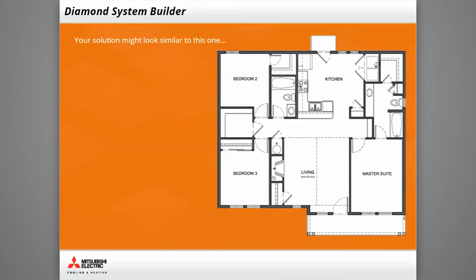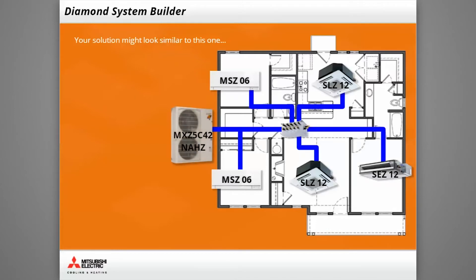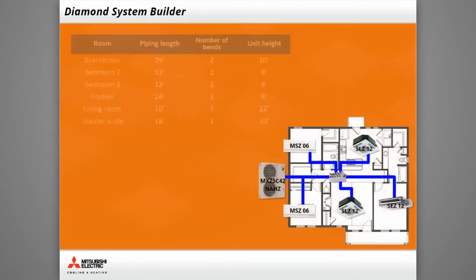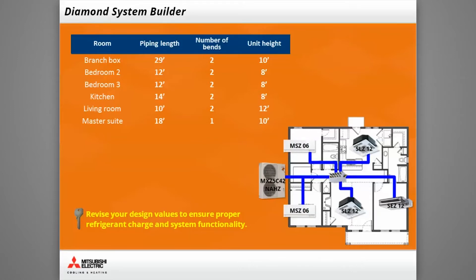Your solution might look similar to this one: MSZ-06s in each bedroom, SLZ-12s in the living room and kitchen, and an SEZ-12 in the master suite. Outside, an MXZ-5C42 hyperheat with a branch box. In addition to the units, your design will also include line set lengths, number of bends, and unit heights. Before installation these values are generally estimated, but once installed you should revise these values to ensure the proper refrigerant charge and functionality of the entire system.